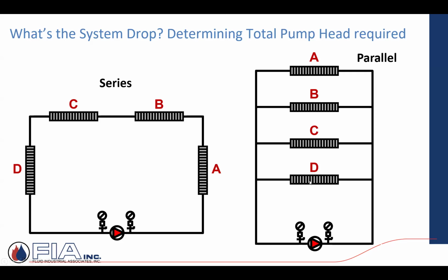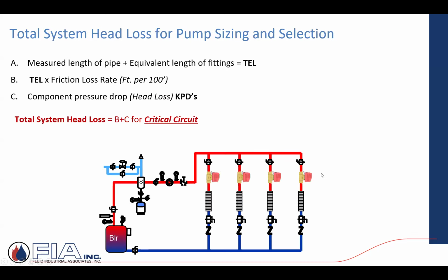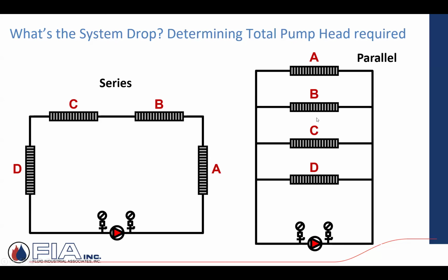But I wouldn't have to add in the pressure drop of D and C and B in addition to the pressure drop of A. I just have the pressure drop of that circuit that feeds A, but the total flow rate of D, C, B, and A. So the pump has to move all that flow because all four zones could be calling, but I only have to overcome the pressure drop of the one with the greatest resistance. Don't add them all up because then you're overheading. You're having a pump that's way too big. And then when you put that pump on and it doesn't know it's too big, it's just shoving way too much water throughout your whole system. You're oversized, overpumping. You don't want to do that.